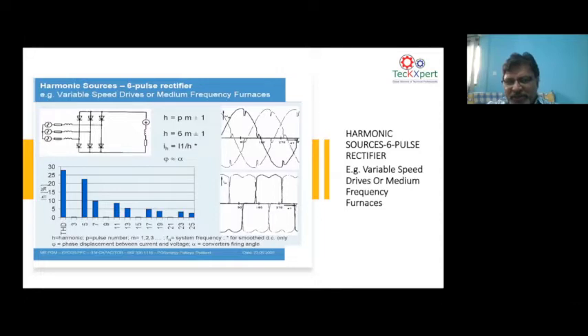That means when you have this 6 pulse diode bridge functioning, taking the AC and converting it to DC, every time the diode conduction moves from one phase to the other leg of the 6 pulse drive, there is a short circuit taking place. That short circuit does not bring the voltage completely to zero, because ultimately there is a certain amount of inductance and impedance which keeps the voltage from falling to zero, but then you get a notch on the wave shape. That is why when you go to a 6 pulse AC drive, you sometimes get a voltage waveform looking like a notch and a current waveform looking like those little U shapes. Go to the next.